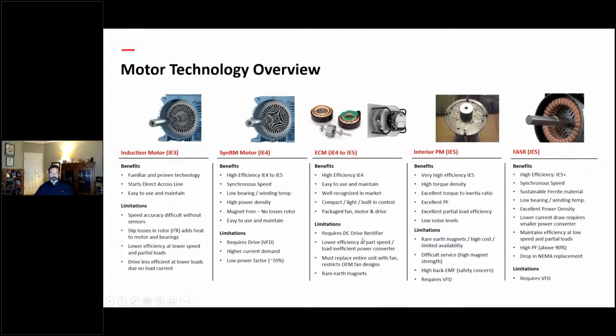But it requires a DC power rectifier, and DC rectifiers are inherently inefficient at light loads. So one of the disadvantages, remember, you're trying to get a flat line efficiency profile at light loads. So if my rectifier or drive is inefficient at light loads, that increases your losses. And so these tend to be a little less efficient at lighter loads than what we'll talk about here with the ferrite assisted motor design.